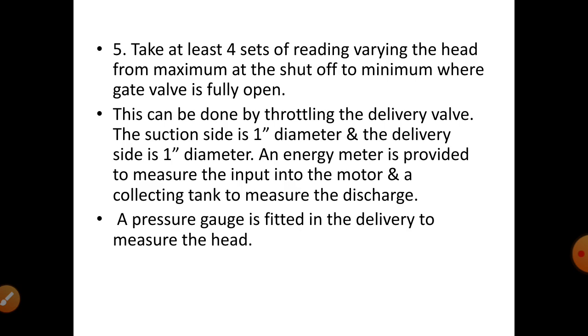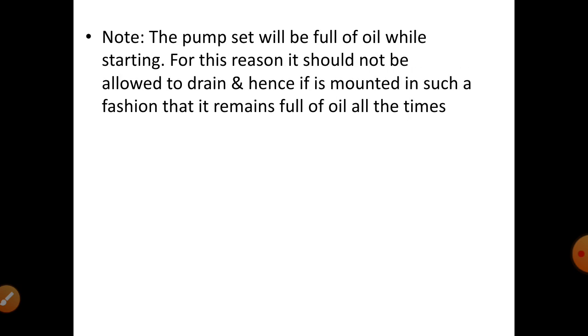This can be done by throttling the delivery valve. The suction side is one inch diameter and the delivery side is one inch diameter. An energy meter is provided to measure the input to the motor, and a collecting tank to measure the discharge. A pressure gauge is fitted in the delivery to measure the head. The pump casing should be full of oil while starting, so it is mounted in such a fashion that it remains full of oil at all times.